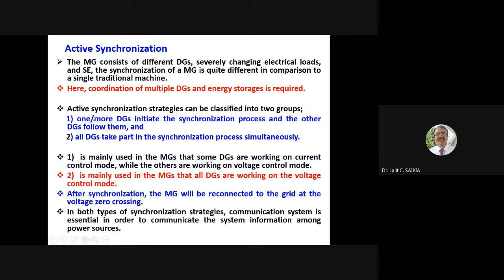One is that one or more DGs initiate the synchronization process, and the other DGs follow them. First, we have to synchronize one unit and the other units follow. Secondly, all DGs take part in the synchronization process. The first is mainly used in a microgrid where some DGs are working in current control mode, while others are working in voltage control mode. The second is mainly used in a microgrid where all DGs are working in voltage control.